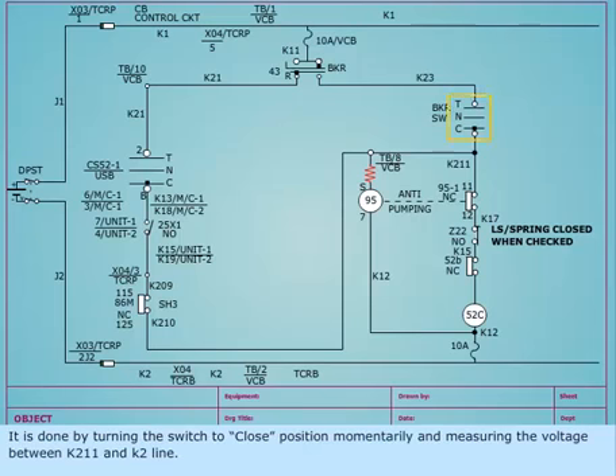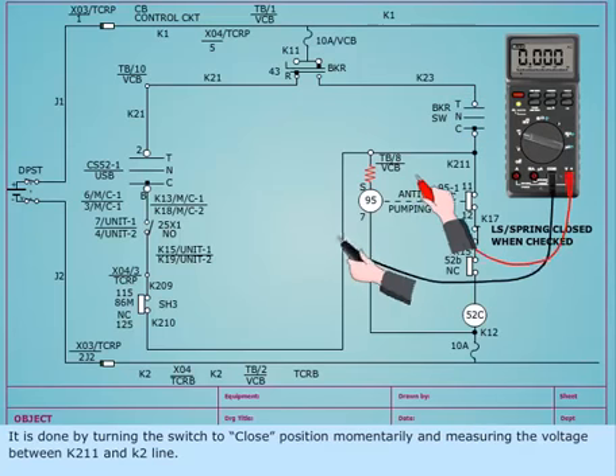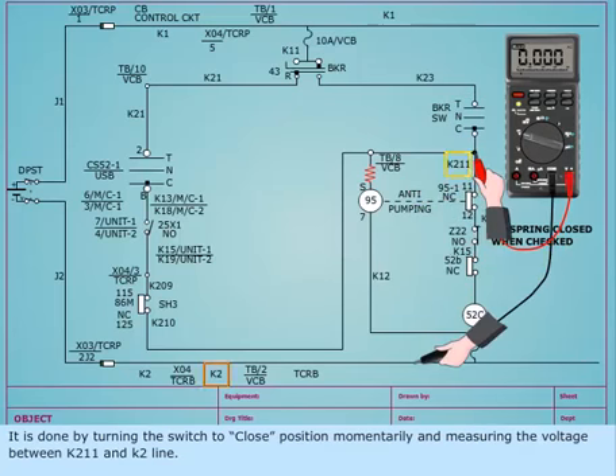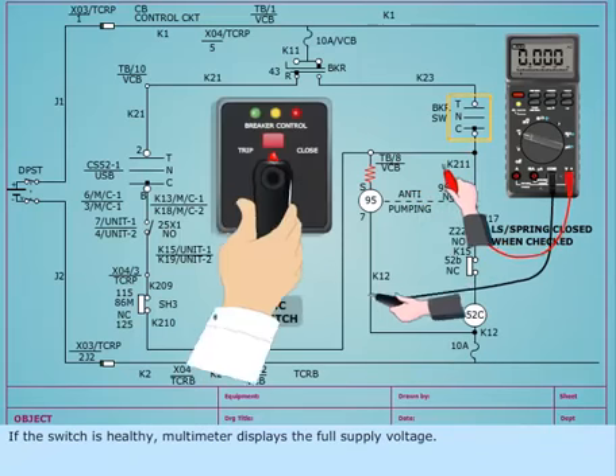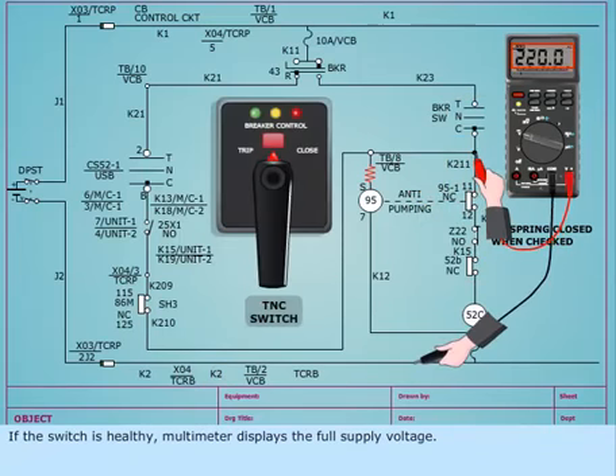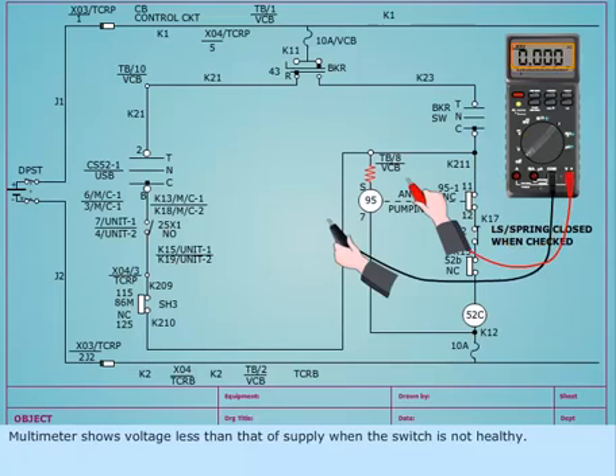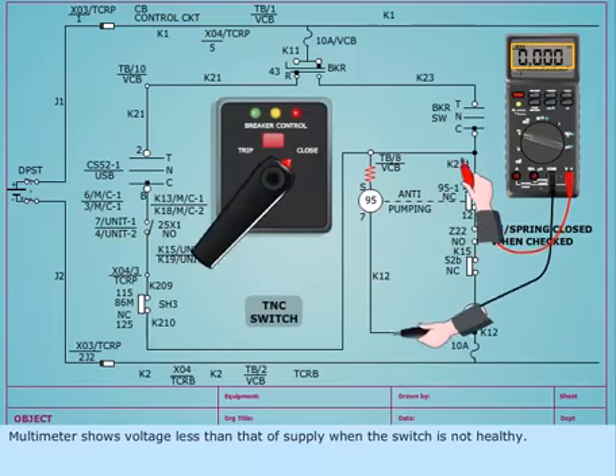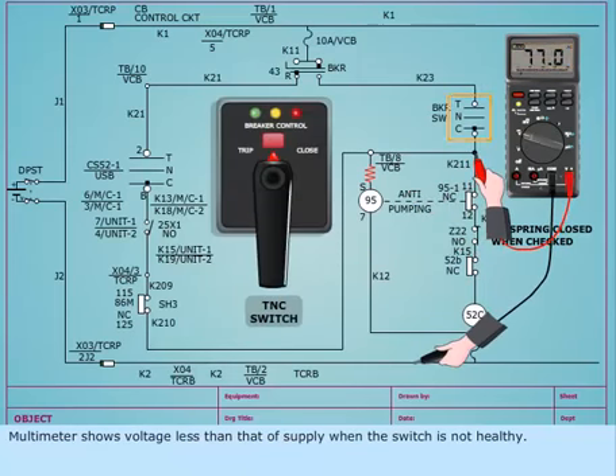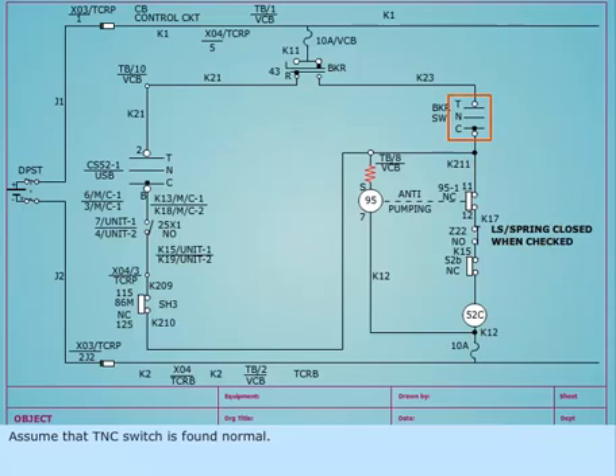It is done by turning the switch to close position momentarily and measuring the voltage between K211 and K2 line. If the switch is healthy, multimeter displays the full supply voltage. Multimeter shows voltage less than that of supply when the switch is not healthy. Assume that TNC switch is found normal.